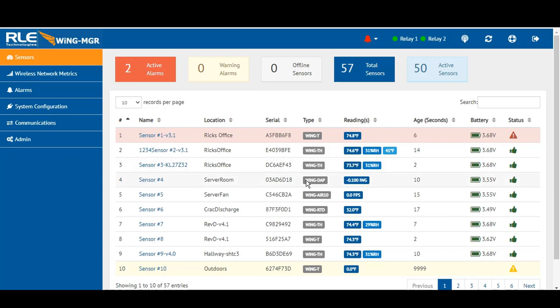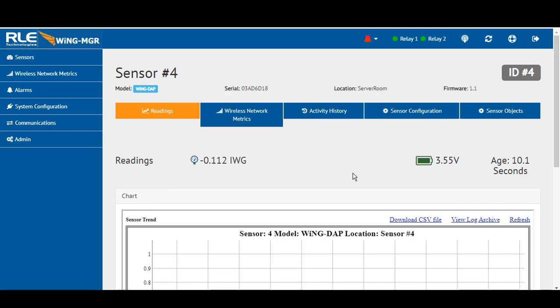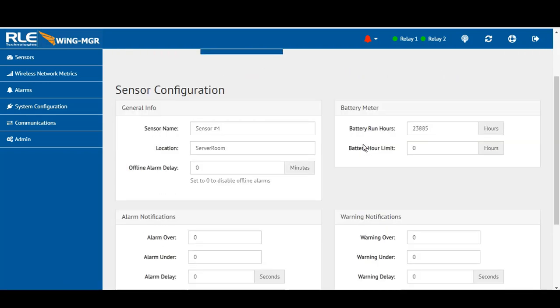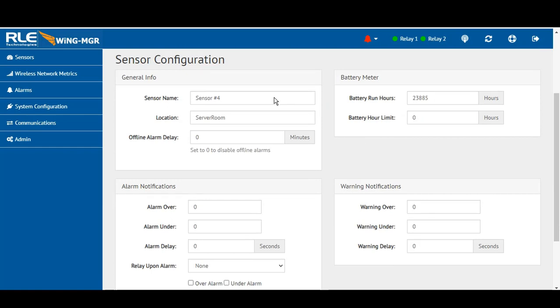All alarm capabilities, email notifications, and trending are available. A few sensors I wanted to focus on today are the Wing DAP — the Wing Differential Air Pressure sensor. Understanding building pressure, positive or negative, in any particular space sometimes isn't as easy or tangible as you'd like. Here's the differential air pressure sensor, capable of providing information to an end user or network group. Getting into the sensor configuration, you can name the sensor, give it a location, and if it falls offline, you can set up an alarm delay of a minute or two to minimize false alarms.